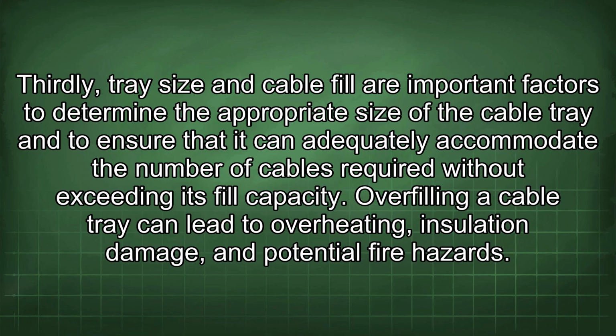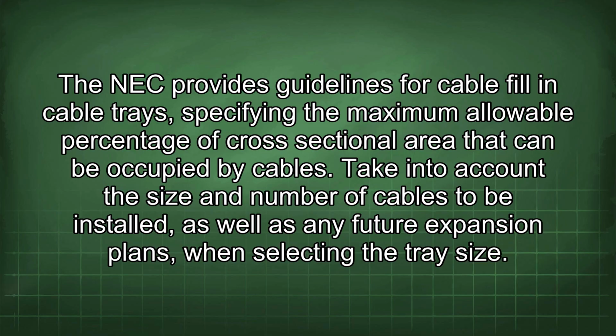Thirdly, tray size and cable fill are important factors to determine the appropriate size of the cable tray and to ensure that it can adequately accommodate the number of cables required without exceeding its fill capacity. Overfilling a cable tray can lead to overheating, insulation damage, and potential fire hazards. The NEC provides guidelines for cable fill in cable trays, specifying the maximum allowable percentage of cross-sectional area that can be occupied by cables. Take into account the size and number of cables to be installed, as well as any future expansion plans, when selecting the tray size.